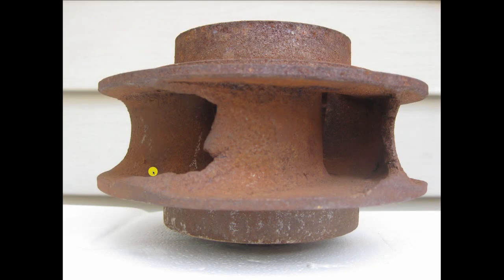And it looks like this in real life. This is supposed to be solid out to the edge here. All of this was eaten up by cavitation. In real life, it sounds like you're pumping gravel. If you want to hear this in real life, if you have a swimming pool, go over to the pool skimmer and stuff a beach ball in while the filter pump is running and listen to what happens. The filter pump is going to immediately begin to cavitate. Don't do that on your own house. Do it on your neighbor's.